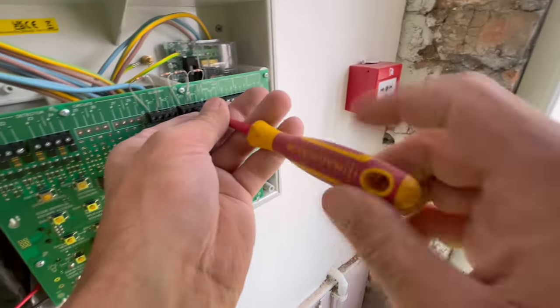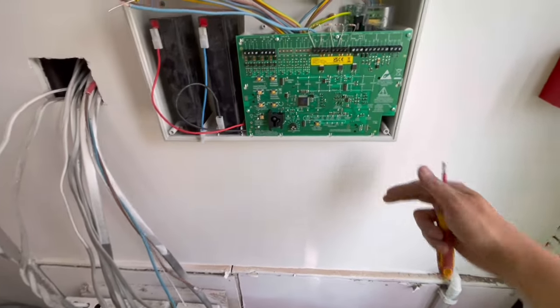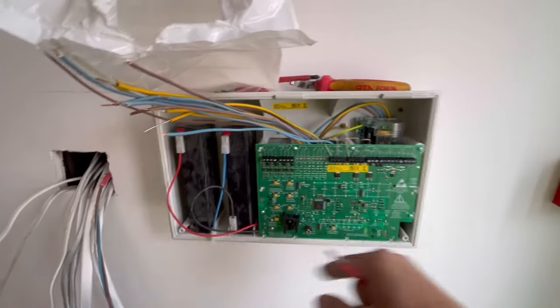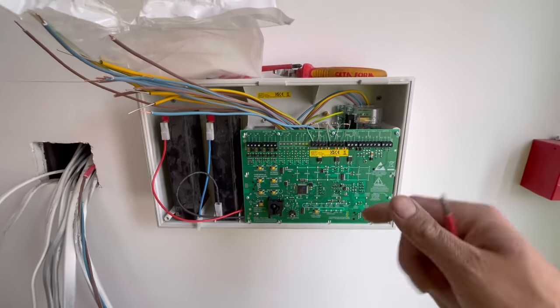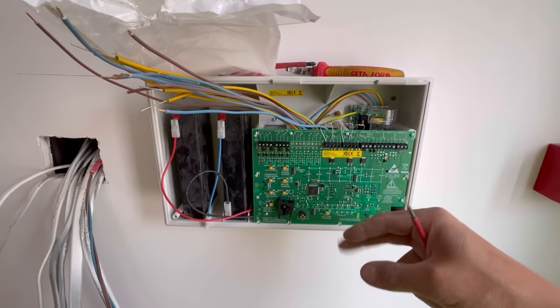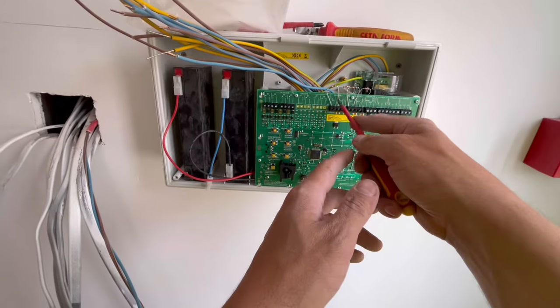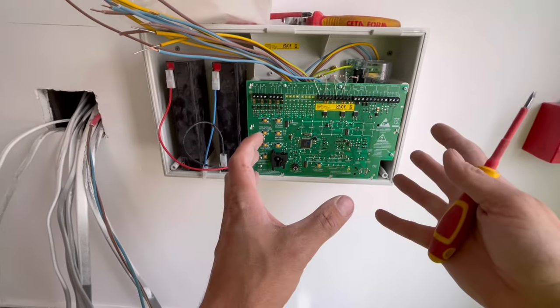So if you imagine that the fire alarm system is a complete circuit, like a light bulb with a light switch. So the light switch is on, and let's just say the light switch is the fire alarm. So how this will work is the light is always on, and then when there's a fire, the smoke detector or heat detector will trip the switch, basically turn the light off, and that's what the board recognises, that there's no current in the circuit, and that trips the board.